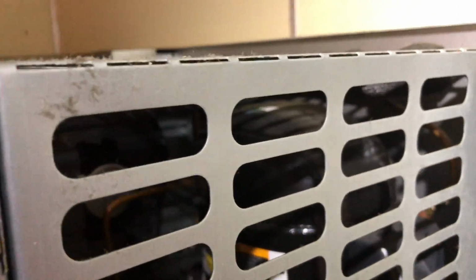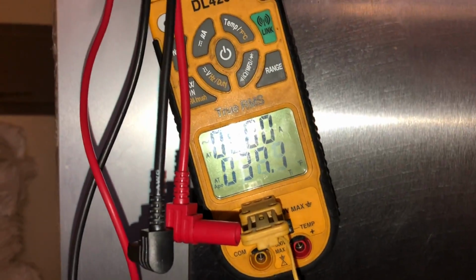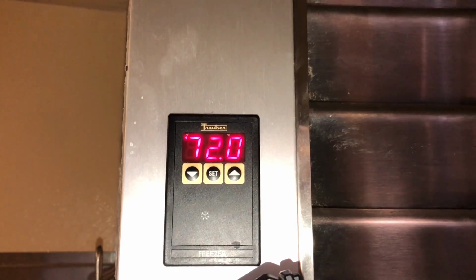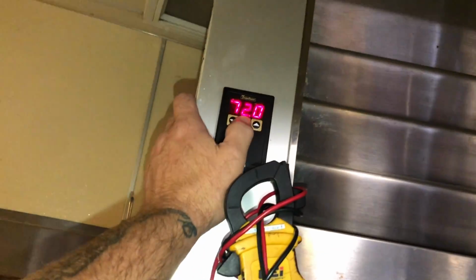responds in defrost. These new Traulsens, there's no taps to gauge up on. The old ones used to have them. These ones don't. But there's plenty of heat rejecting off that condenser, so I'd be thinking the charge is good. But let's let it pull down, then we'll see where we're at. I got the DL429 hooked up with the temperature probe. Box is 37 degrees. My cabinet sensor is showing 72.